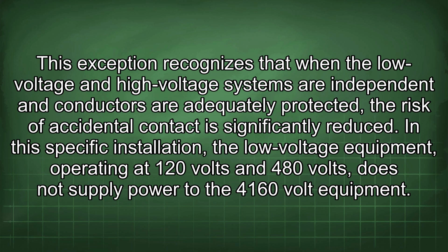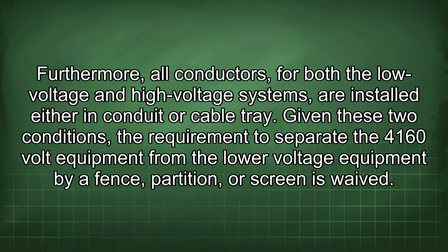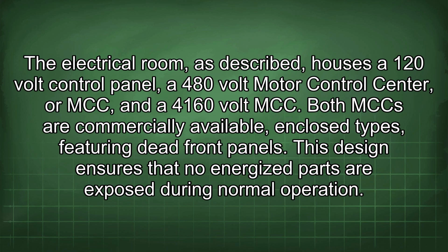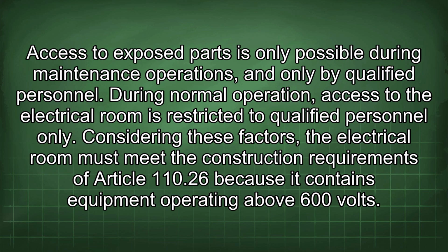In this specific installation, the low-voltage equipment, operating at 120 volts and 480 volts, does not supply power to the 4160-volt equipment. Furthermore, all conductors for both the low-voltage and high-voltage systems are installed either in conduit or cable tray. Given these two conditions, the requirement to separate the 4160-volt equipment from the low-voltage equipment by a fence, partition, or screen is waived. The electrical room, as described, houses a 120-volt control panel, a 480-volt motor control center, or MCC, and a 4160-volt MCC. Both MCCs are commercially available, enclosed types, featuring dead front panels. This design ensures that no energized parts are exposed during normal operation. Access to exposed parts is only possible during maintenance operations and only by qualified personnel. During normal operation, access to the electrical room is restricted to qualified personnel only.